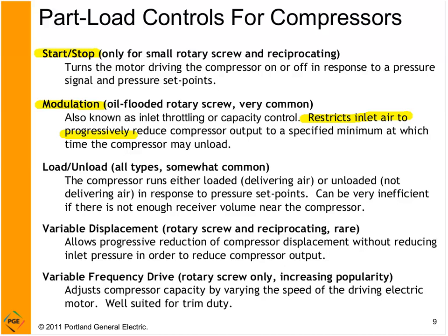Modulation literally means to regulate or modulate the flow through the machine by restricting the air inlet — like stuffing a sock in a carburetor air cleaner, reducing airflow. Very effective but not very efficient. Load/unload operates by pressure dropping to a set point, loading up and pressurizing the oil sump, pushing air to discharge. Once it pumps up to higher pressure it unloads, dumping sump air — like putting your car in neutral at a stoplight, idling but using very little fuel.